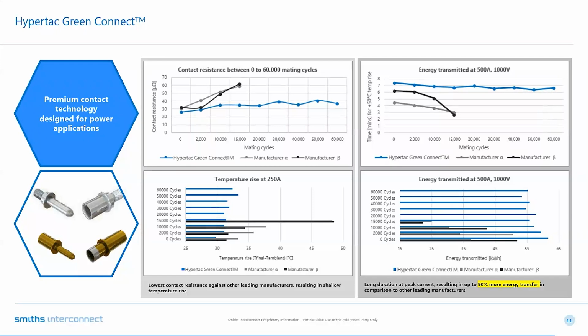Just before I leave this slide, I'll leave some numbers with you so you can really picture the gravity of the problem we have on our hands. A rise from 30 microohms to 60 microohms of contact resistance at 500 amps results in a power loss increase from 7.5 watts to 15 watts per contact. This doubles the amount of local heat generation - that's where the problem lies.